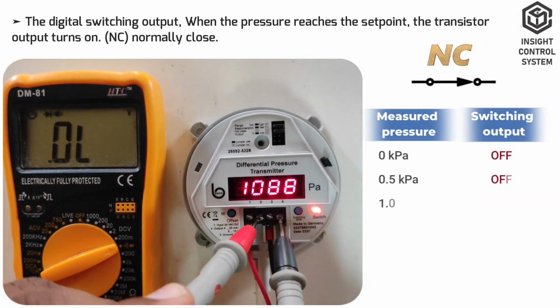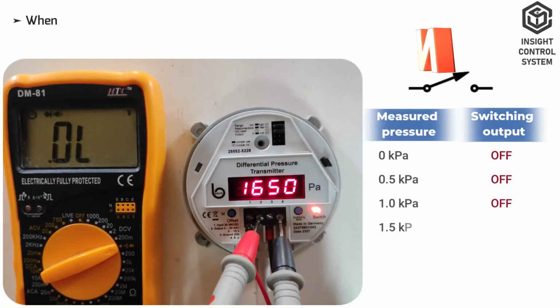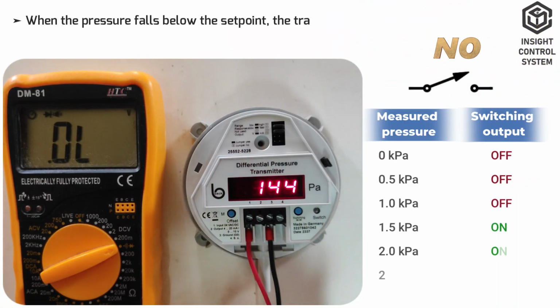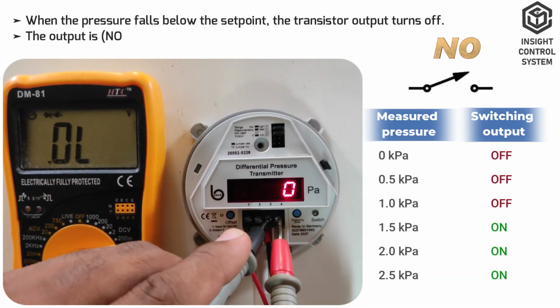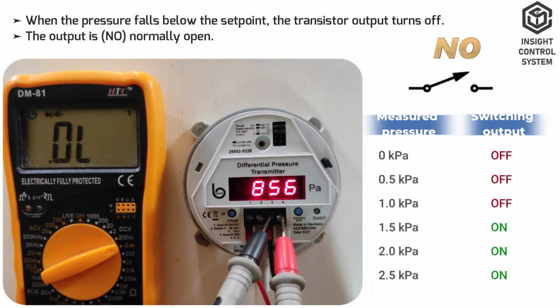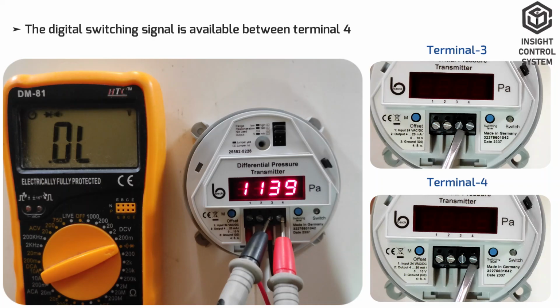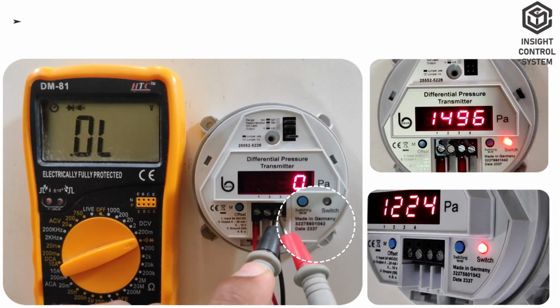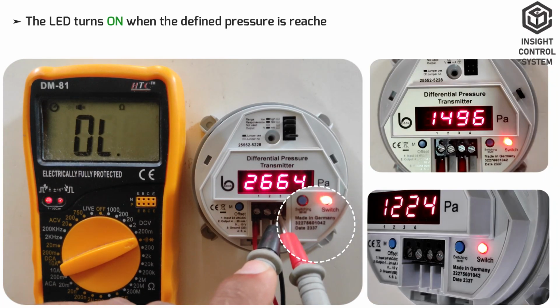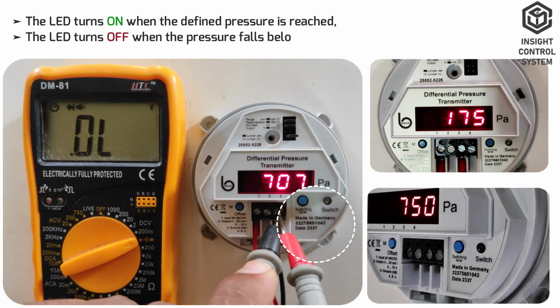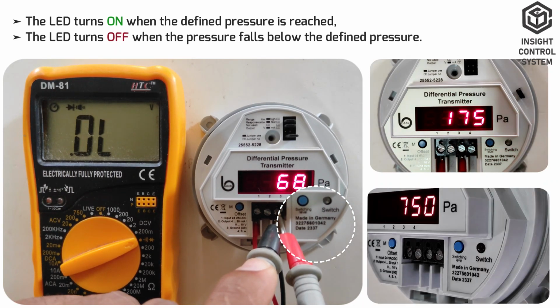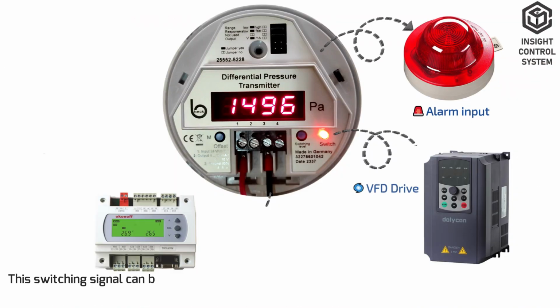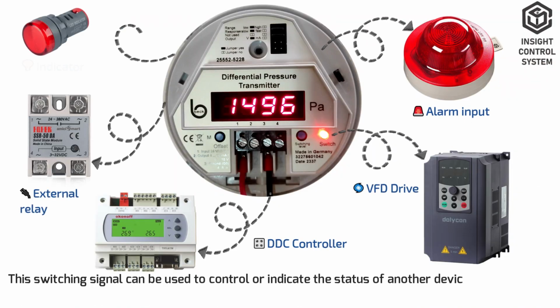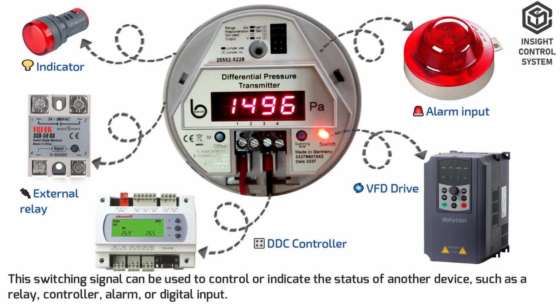The digital switching output: when the pressure reaches the set point, the transistor output turns on. When the pressure falls below the set point, the transistor output turns off. The output is normally open. The digital switching signal is available between terminals 4 and 3. The LED turns on when the defined pressure is reached, and the LED turns off when the pressure falls below the defined pressure. This switching signal can be used to control or indicate the status of another device, such as a relay, controller, alarm, or digital input.